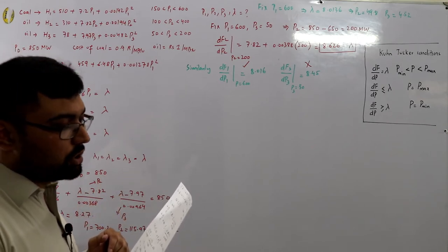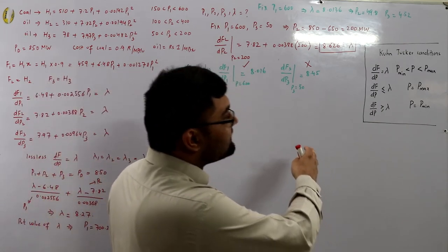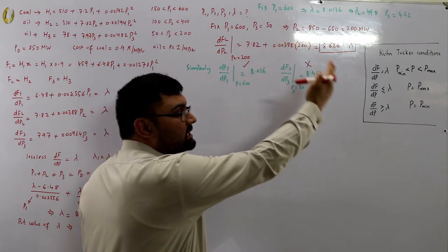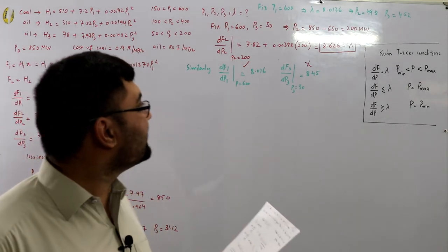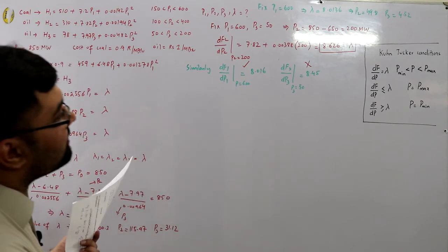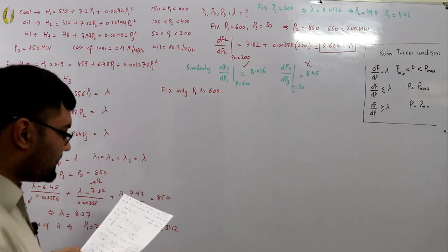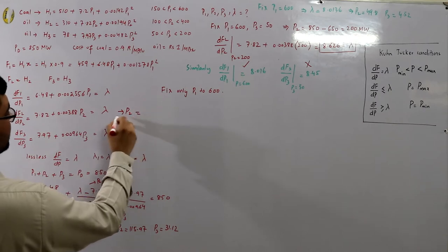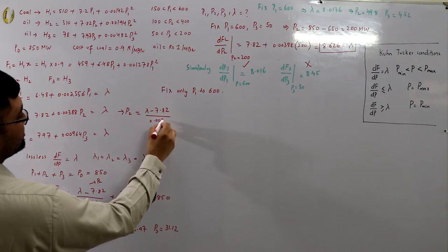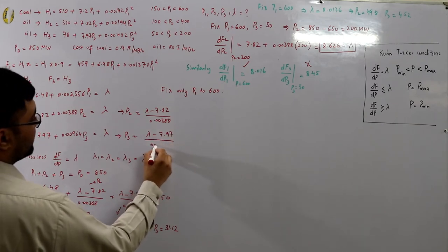Since the Kuhn-Tucker condition for p3 at minimum is not satisfied, we only fix p1 = 600 MW and leave p2 and p3 free. From df2/dp2 = λ: p2 = (λ − 7.82)/0.00388. From df3/dp3 = λ: p3 = (λ − 7.97)/0.00964.